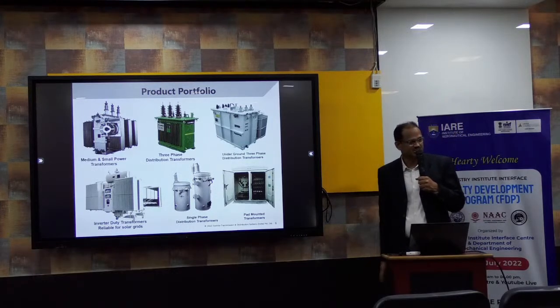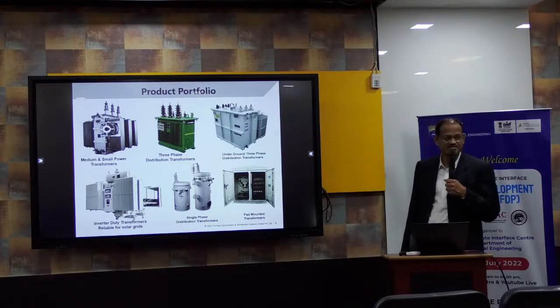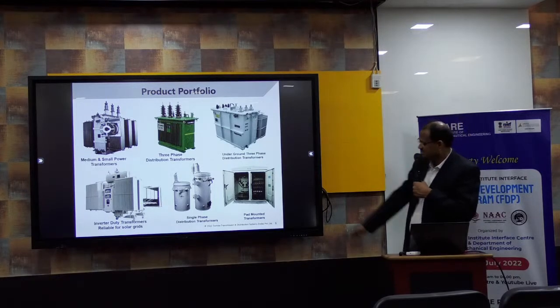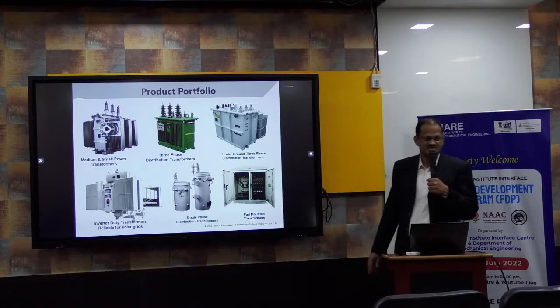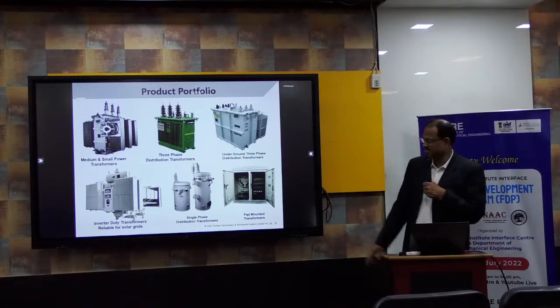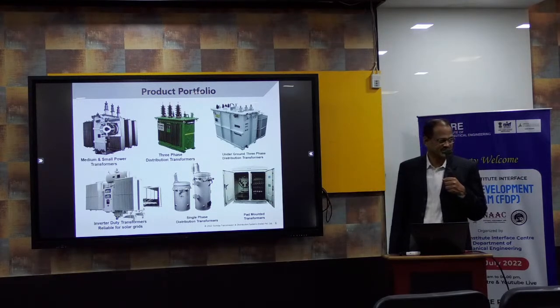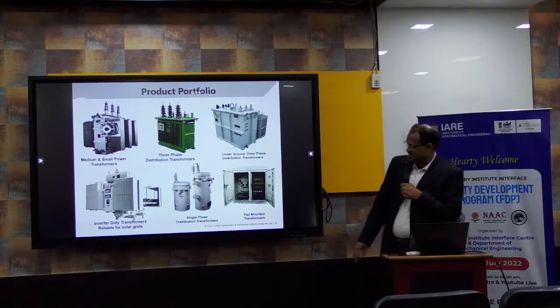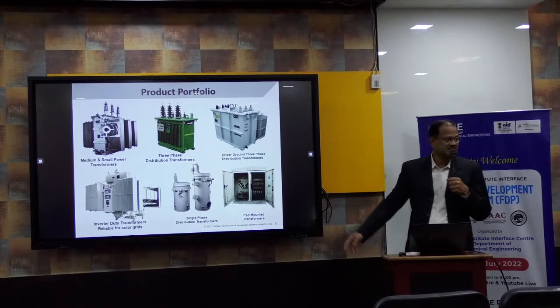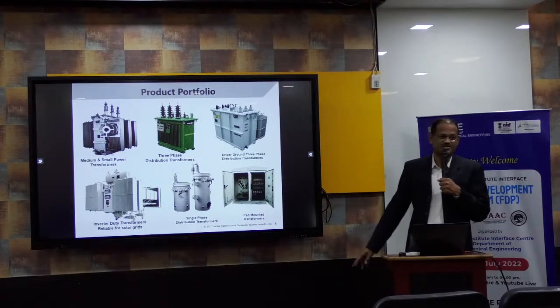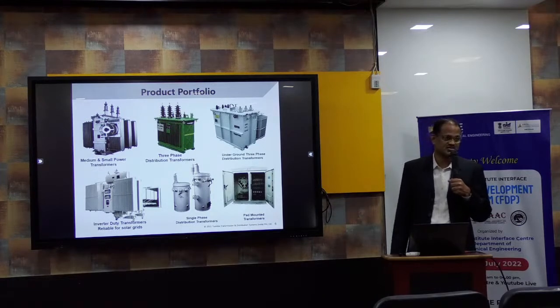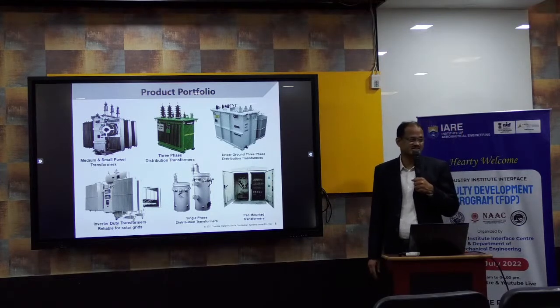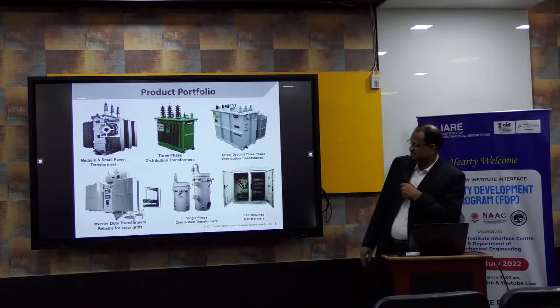Sometimes they mount the transformer in the underground like railway stations and all. Suddenly rain, water has entered the transformer, nothing will happen to the transformer. That's the technology. This is a pad mount transformer. Now India is just gearing up to install this kind. Normally in the US, this kind of transformer you can see very frequently. Completely in the external world, they will install it next to their house, directly on the ground. You can touch whatever you want to, you can do on the transformer, so no electrical shock to any person. So the highest safety level will come with the pad mounted transformer.